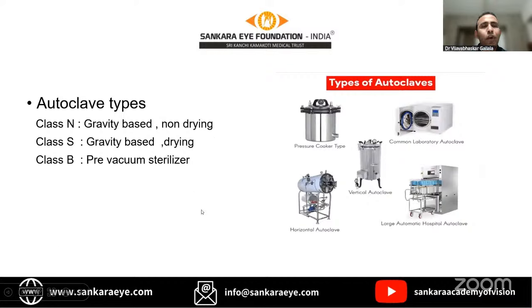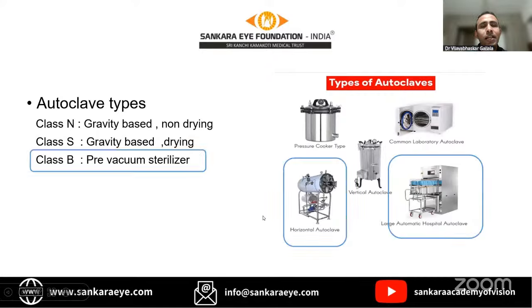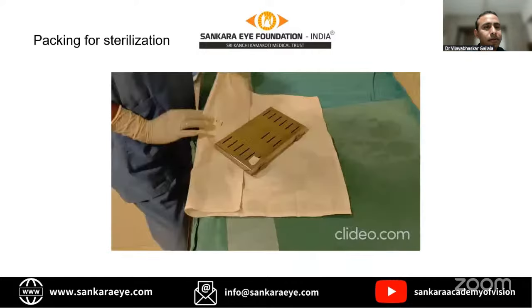There are different types of autoclaves. Based on the design, there are pressure cooker, vertical, horizontal autoclaves, and table-top autoclaves. Based on their mechanism, there are class N, S, and B types. The most effective ones are pre-vacuum sterilizers, where the vacuum generator is separate and the steam generator is separate, which is more effective in sterilization of instruments compared with other types of autoclaves.